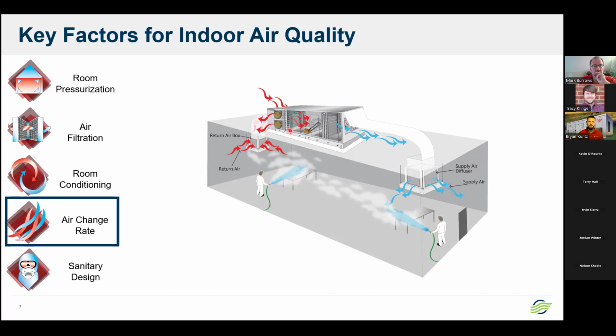We typically like to see an air change every 3 minutes to make sure we're grabbing as much moisture as possible and evacuating it out of the space, through either our integrated exhaust fans that you can see shown in this picture or through remote exhaust fans. Either way, you want to get that air out of these rooms. So that's definitely a big piece to making sure that production can come back in the morning and get started right away.